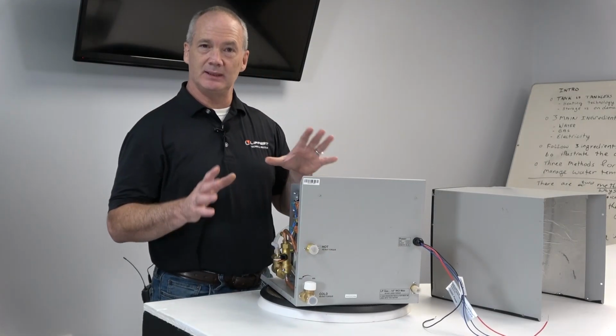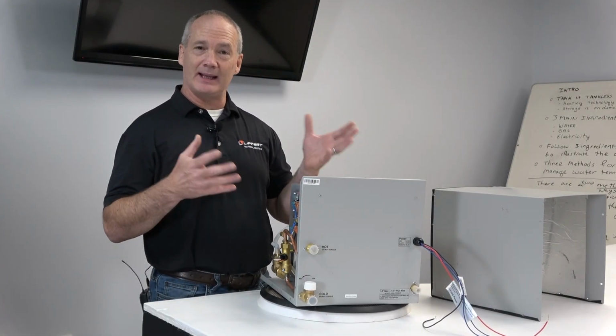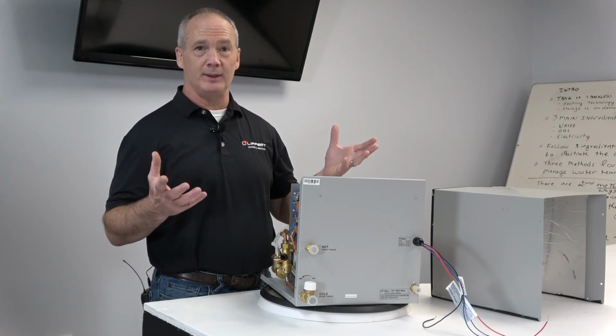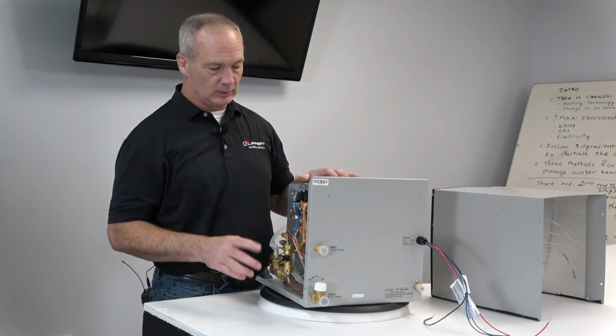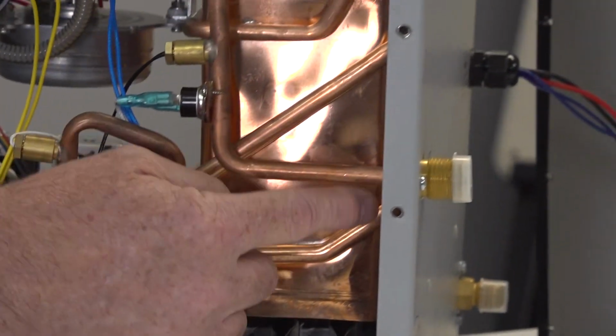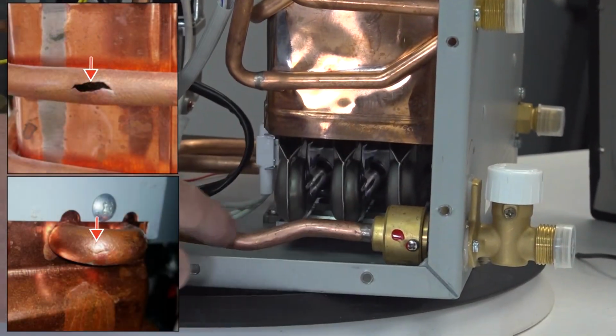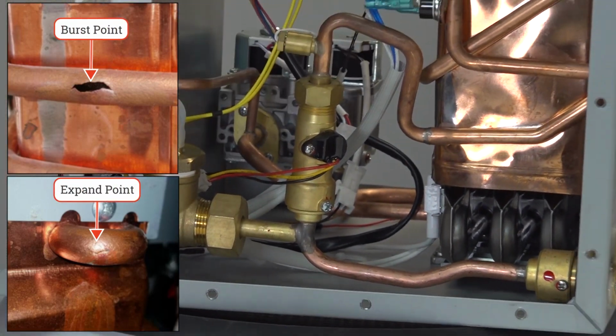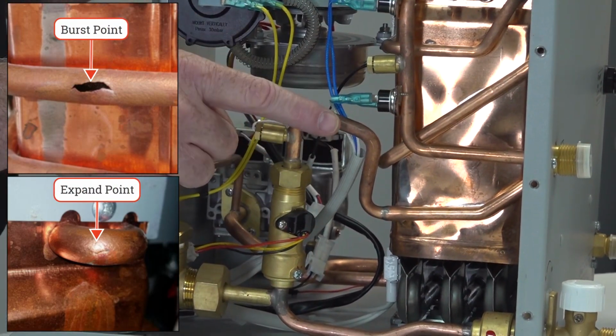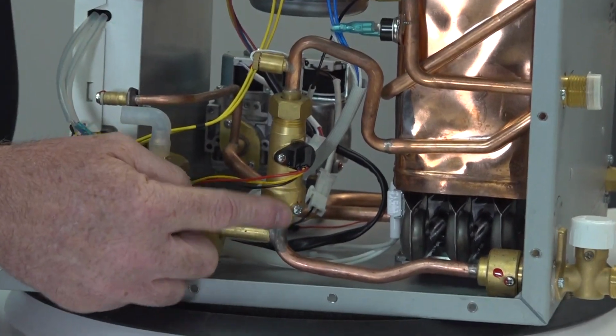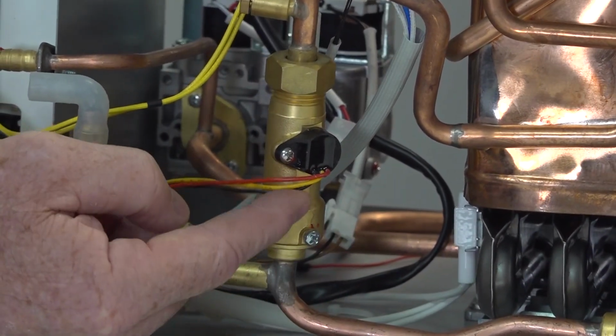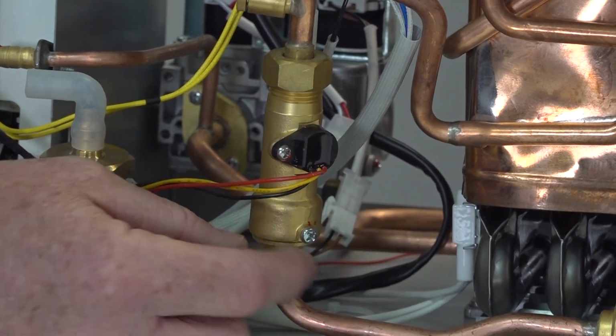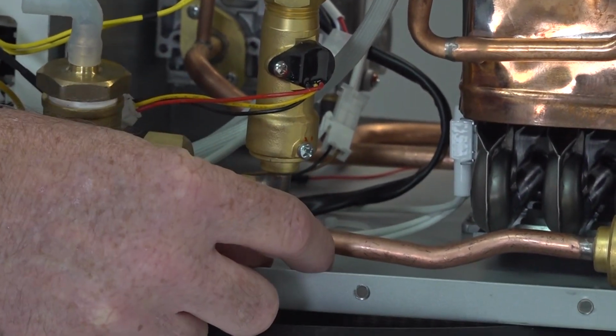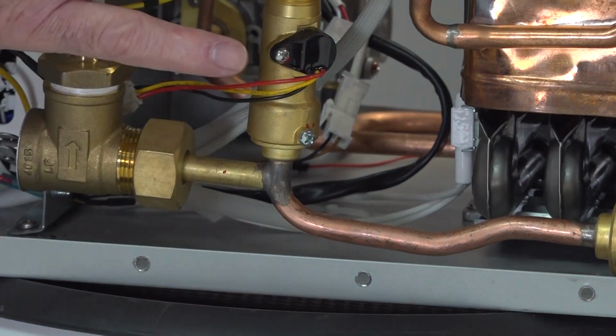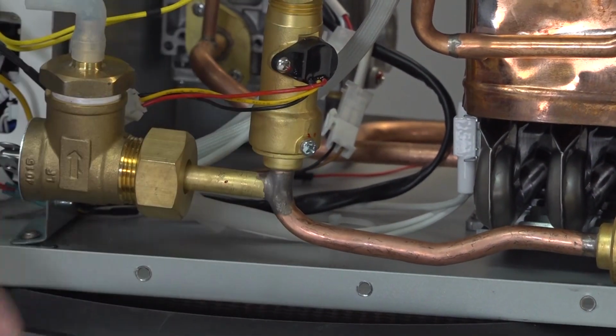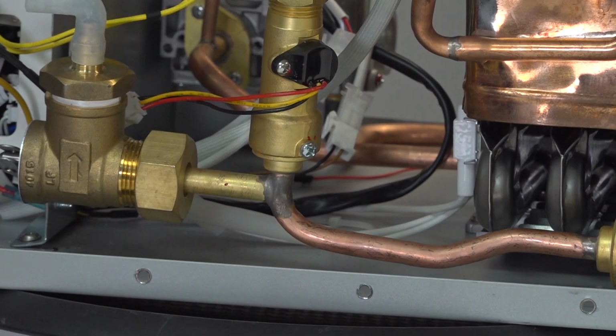Our next inspection is looking for freeze leaks. Now that could happen if you get surprised by a winter day or it wasn't winterized properly. What you're looking for is these pipes and anywhere in the appliance where there's water that could be stuck in a tube, and it could burst a tube. Another thing it can do is it can force this water flow sensor to break this screw and push the inlet tube off of there. So you're just looking for burst tubes and that water flow sensor to be forced off of there.